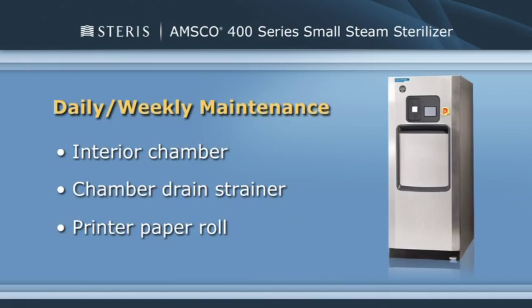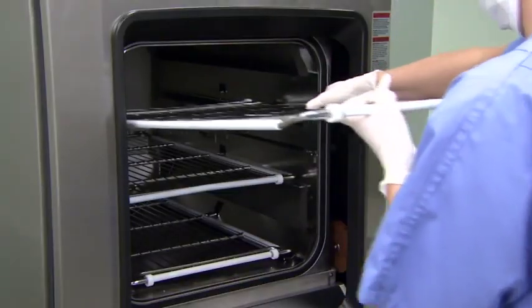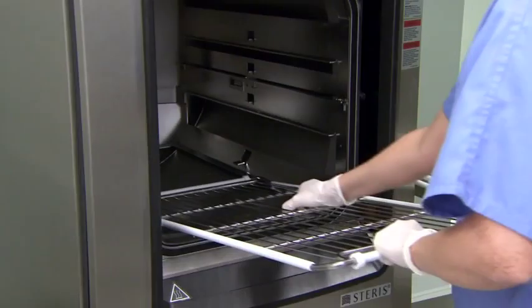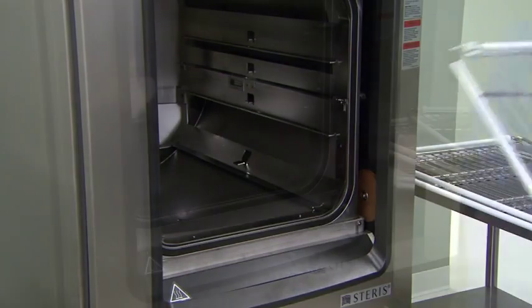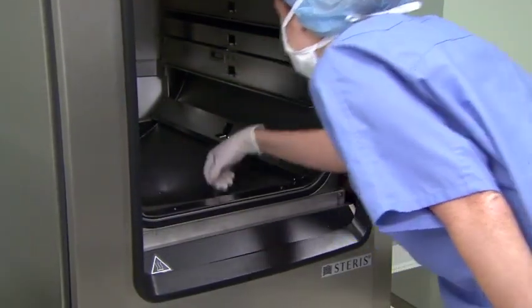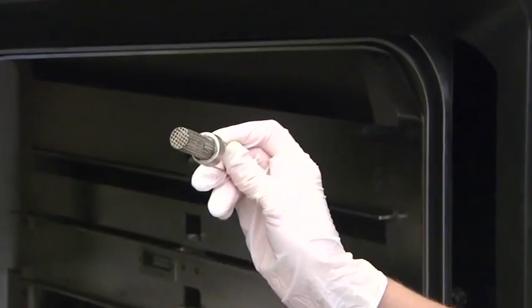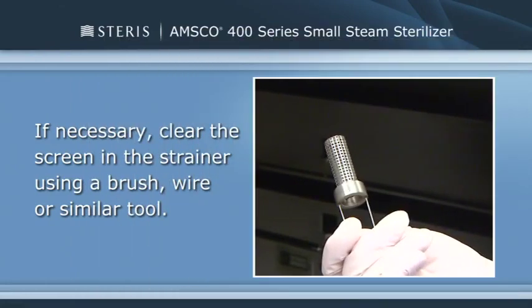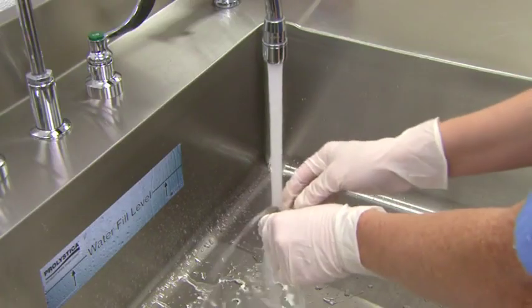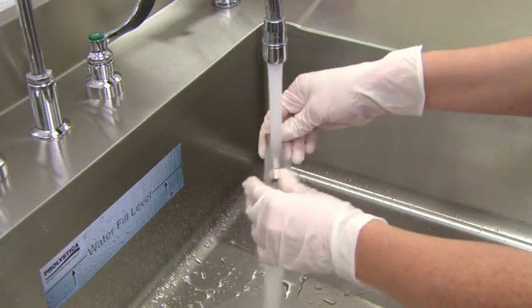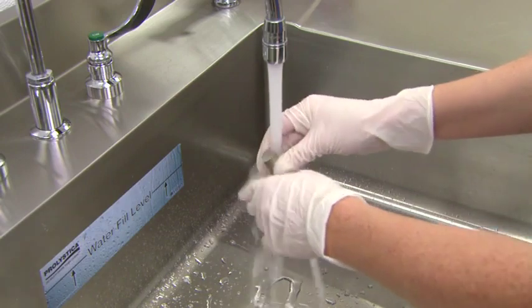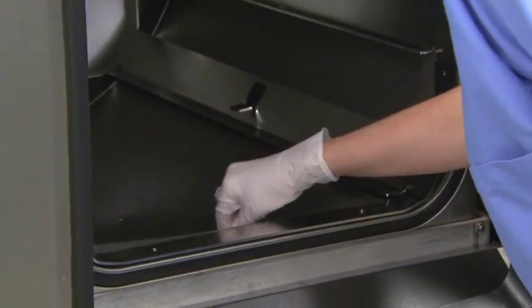STERIS recommends inspecting the interior chamber and chamber drain strainer each morning before running the daily warm-up cycle. Start by cleaning the chamber drain strainer, preferably after the final cycle of the day has been run. Remove it from the drain in the bottom of the chamber. Remove any obvious debris, and if necessary, clear the screen in the strainer using a brush, wire, or similar tool. Once it has been cleared of obvious debris, reverse flush the strainer under running water. Replace the strainer in the chamber drain.